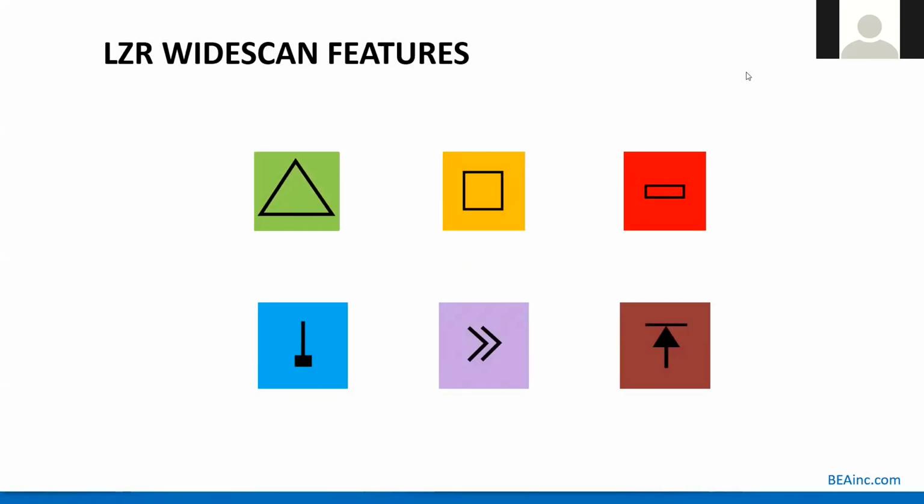So the sensor exercises 3 functions. Among them, that's activation in green, object presence in yellow, and human safety in red. These are what we refer to as the 3 primary functions. Therefore, the sensor has 3 relays. Then we have additional features that are the virtual pull cord, the motion speed, and the height trigger. These are what we call the added value features, meaning that they are designed to enhance the performance of a certain property or field, that being the activation circuit.